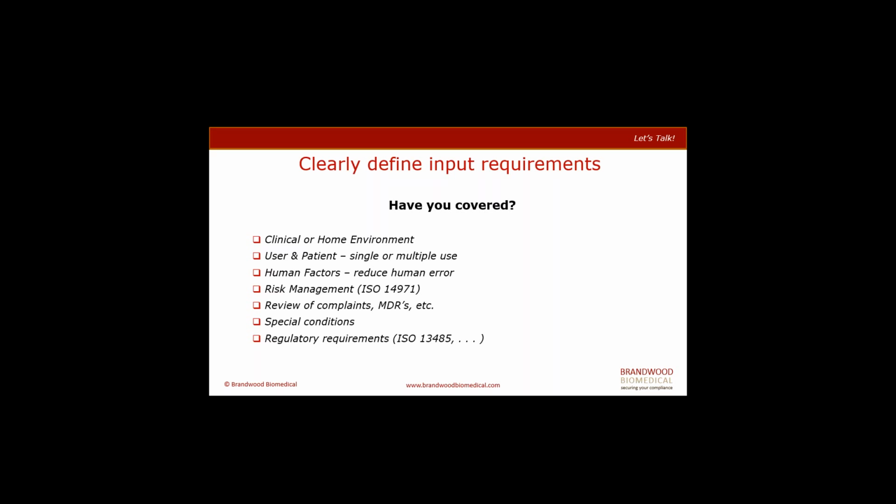From a regulatory perspective, medical device reports, for example, the MAUDE database, go through those to identify whether there's any specific areas or issues that have been identified through other manufacturers' devices that could help with the input into the requirements of your new device. Any special conditions you may have. And most importantly, the regulatory requirements, such as 13485.